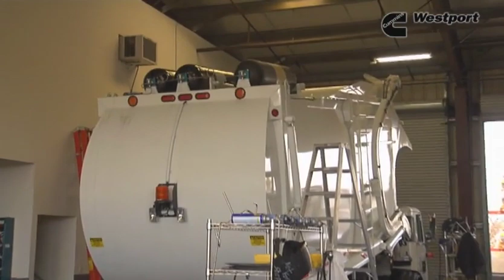A CNG fuel system will utilize CNG stored in fuel tanks under pressures of up to 3,600 psi at 70 degrees Fahrenheit or 21 degrees Celsius. Typically, CNG tanks have a capacity of 15 to 25 diesel gallon equivalent per tank, and often there will be 3 or 4 tanks packaged as a fuel system on a vehicle. For extra capacity, there are also larger tanks up to 40 diesel gallon equivalent that can be mounted on the vehicle frame.